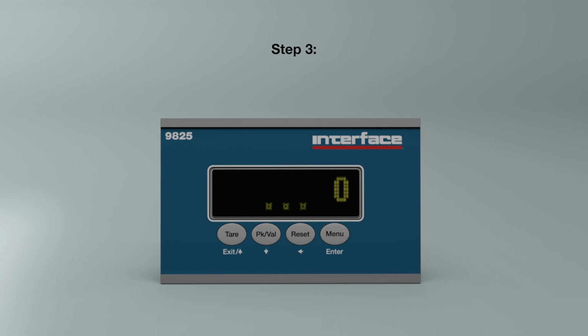Step 3. Hold the menu key down for 2 to 3 seconds to enter the setup menu. The 9825 will make a beeping sound upon entering the setup menu and the first menu item, data capture, will be displayed. Press the menu key to scroll right to the next menu item called Units, then press the peak and valley key to enter the Units submenu.